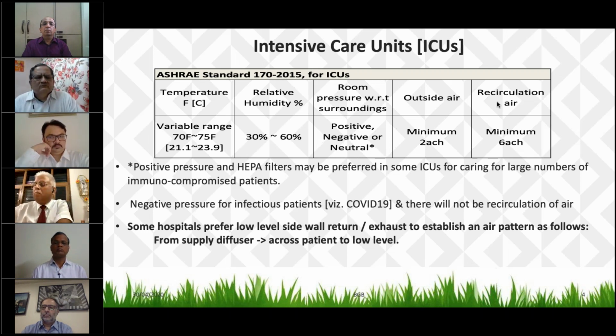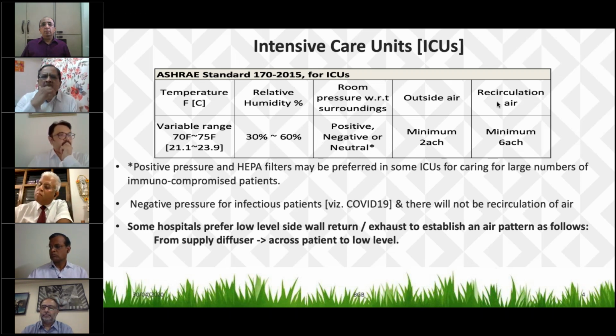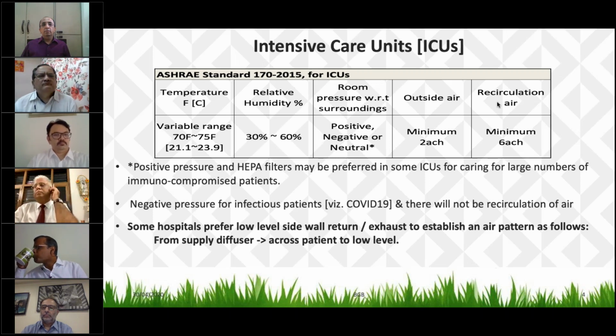Now we'll talk of some specific types of intensive care units. The positive pressure ones are for caring for large numbers of immunocompromised patients. And if it is for COVID patients, then the whole thing has to be under negative pressure, and no recirculation of air is acceptable. As a general practice, the return air has to be towards the lower side of the room. So this is the basic detail of converting it to a COVID type, negative pressure. Next slide.